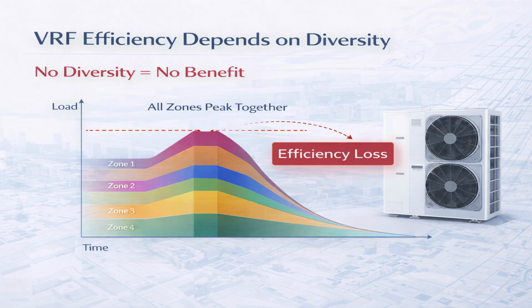One of the most common misunderstandings in VRF design relates to diversity. The system efficiency of a VRF relies heavily on the assumption that different zones will peak at different times. Some spaces cool down earlier, others later, and the system continuously modulates to match that varying demand. When this diversity actually exists, a VRF system performs very well.